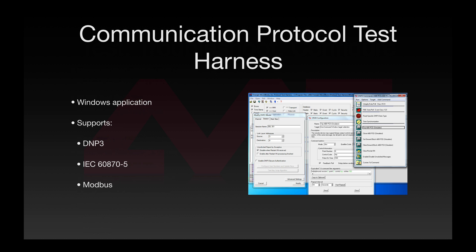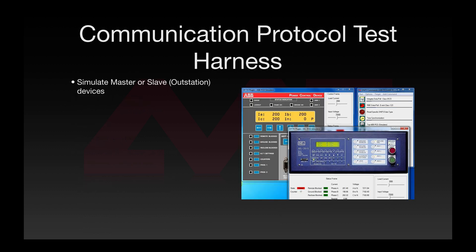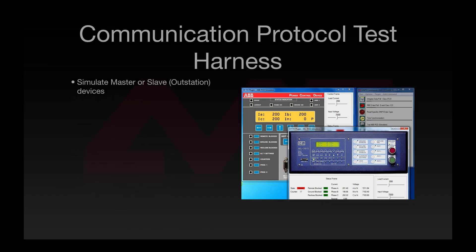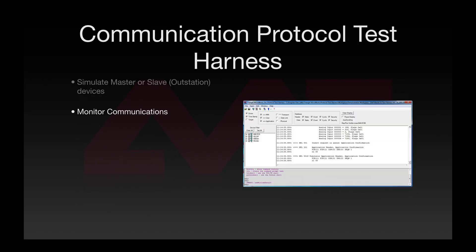The Communication Protocol Test Harness is a Windows application that supports DNP-3, the IEC-60870-5 family, and Modbus. The test harness can simulate both master or controlling stations and slave, also called outstation or controlled station devices. Depicted here are two outstation device simulations complete with front panel emulation and a master control window. The test harness can also be used to monitor communications on both serial and TCP/IP channels.